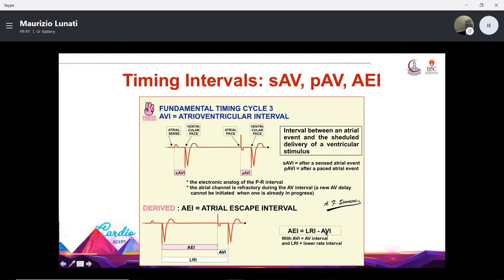Fourth, the postventricular atrial refractory period. What is the postventricular atrial refractory period? It is the interval after a ventricular paced or sensed event during which a natural atrial event cannot initiate a new AV interval. It is the distance between the ventricular pace and the end of the T wave. It is extremely important because with the postventricular atrial refractory period, we can avoid the inappropriate atrial sensing of ventricular events. We can eliminate sensing of retrograde P waves from ventricular conduction. And derived from the postventricular atrial refractory period is the last timing cycle, which is the total atrial refractory period, which is the AV interval plus the postventricular atrial refractory period.